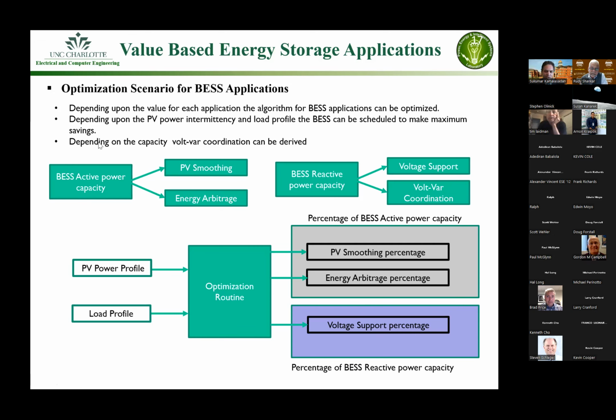As we discussed before, this may have a direct monetary value, but the reactive power does not have a monetary value as such by itself. That's the biggest challenge. So can you relate that to a monetary value by connecting it to the watt, or the real power, of the distribution system or the device? That's something we can do. There is something called volt-var-watt support, so you can do voltage, var and watt connected together. There is a tight correlation in the distribution system because the X by R ratio of the distribution system is low, so that is another aspect that we can utilize. But in any case, there are two different functionalities.